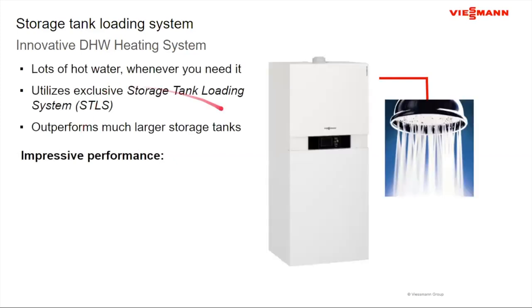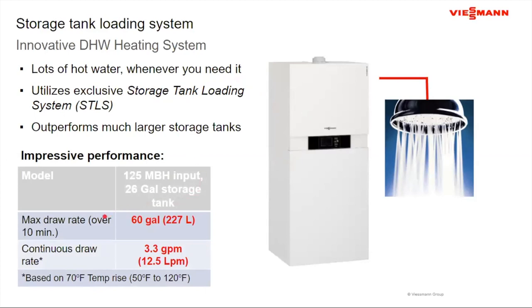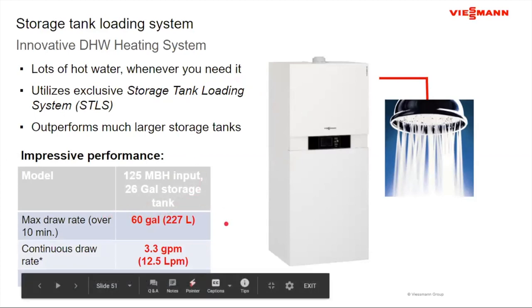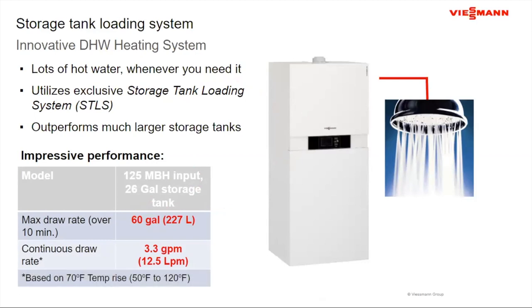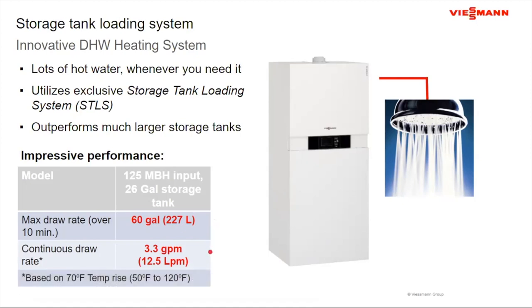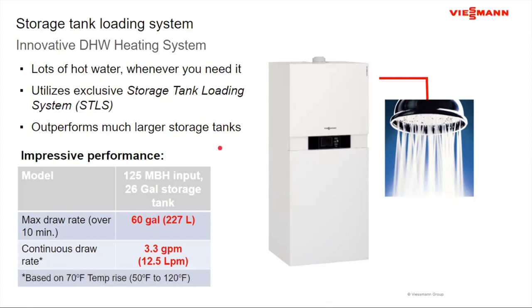So the end result is with this style of system, it's a single footprint, single device, but it gives me a lot of hot water because of this storage tank loading system, which gives me performance much better than much larger storage tanks. From a performance standpoint, over 10 minutes, I can get about 60 gallons of usable hot water from the storage tank coupled with the heat exchanger's performance as well. So you won't find that kind of number out of anything of this size, out of a 125,000 input appliance. And when the tank is all exhausted, I still can draw at 3.3 gallons per minute based on a 70 degree rise. So it gives me a great combination package for very specific applications.